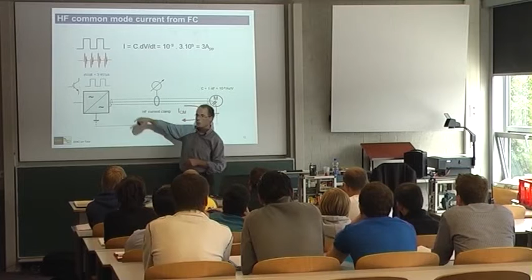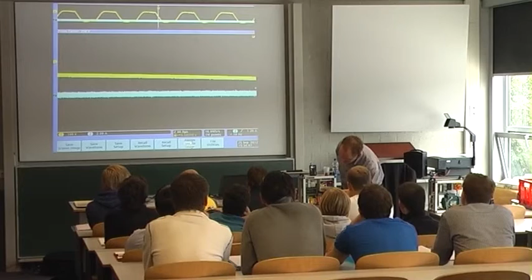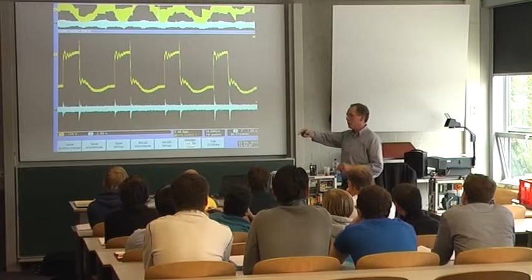Let's see what happens. So I've got two measurements. I will actually show you the voltage. So when I switch on the variable speed drive, I've got two channels. I enlarge this picture, and I will show like this. So it's actually the same as what you saw in Fritz's demo. Square wave in a few hundred volts, so 300 volts going up and down. And the current, which I'm measuring here with the clamp, shows you values of, let's see, well, 6.5 amp, peak to peak. So it's more or less what we can calculate.